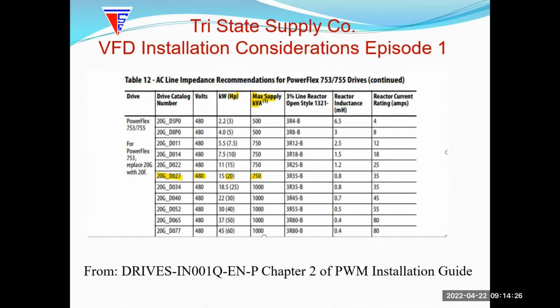Another reason, just for cheap insurance, of putting a reactor in front of the drive is it helps provide protection to the front end of the drive on spikes for maybe nuisance over voltage trips, or for sags especially, because when your voltage sags, you put stress on the rectifier front end of the drive. So that could help prolong the life of your drive as well. So not a bad practice to do it. But if it's over 750, it's highly recommended by Allen Bradley to do so.